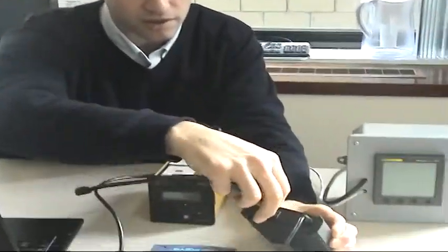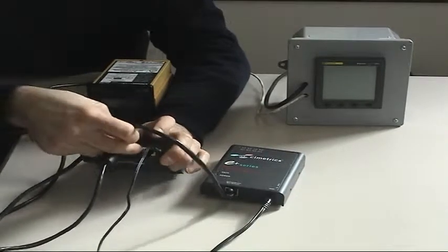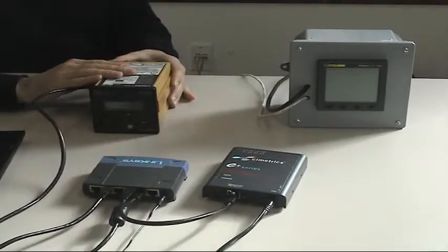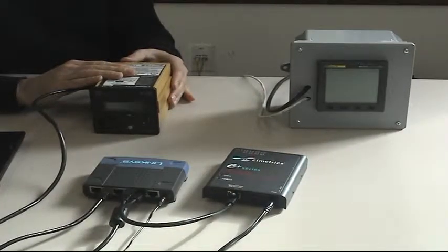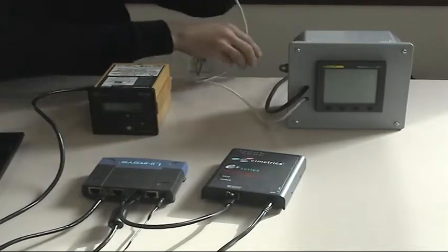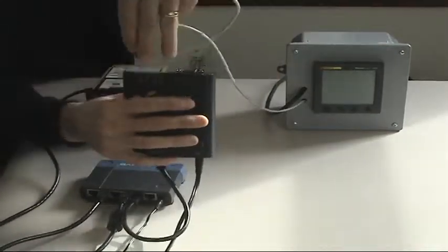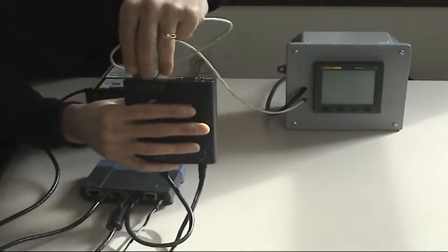After you've configured your EasyMap with an IP address and meter information, you can then connect it to the network. You connect the EasyMap to a network which may have Modbus TCP meters connected to it, and that way the EasyMap will be able to pick up the information from the Modbus TCP meters. If you have Modbus RTU meters, you can connect the Modbus RTU using RS-485 directly to the back of the EasyMap.